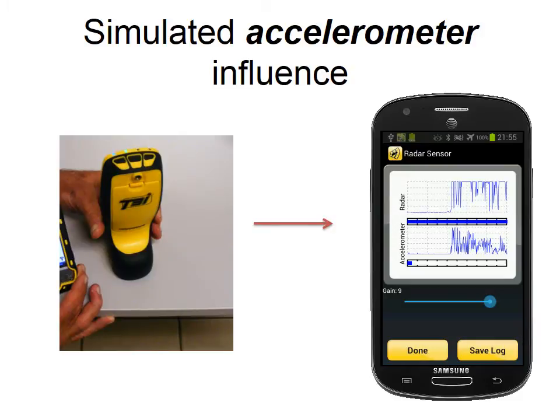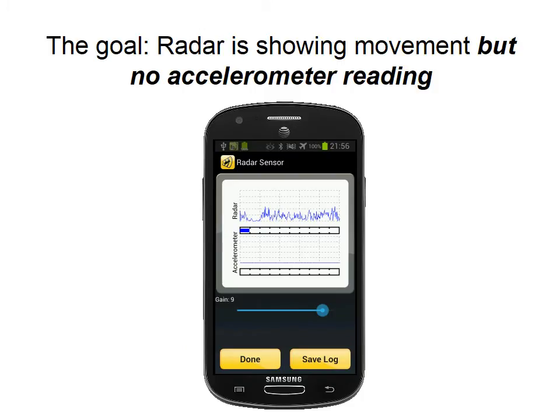With accelerometer movement we will get patterns in the lower screen. Now if you have patterns in the lower screen, that is indicating outside influence of the machine, not actual motion detected by the radar. In this instance you'd have to discount what you're looking at on the screen until you have no movement in the accelerometer shown. The idea is to have a screen that we're looking at here. Full motion in the radar section, flat line in the accelerometer.